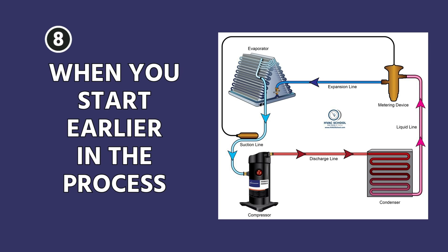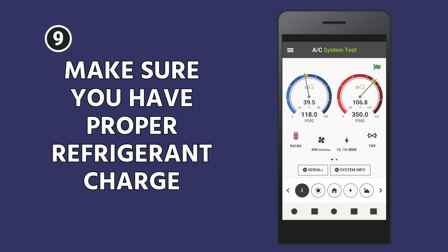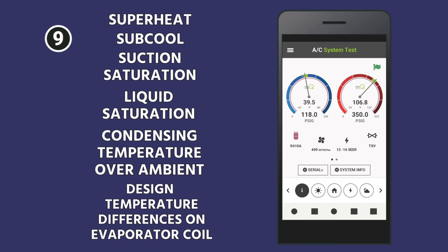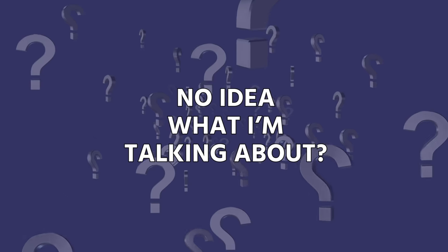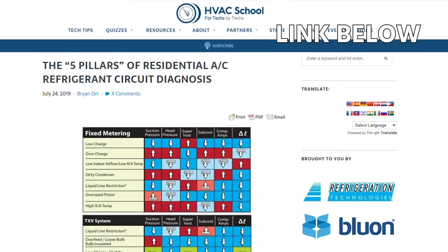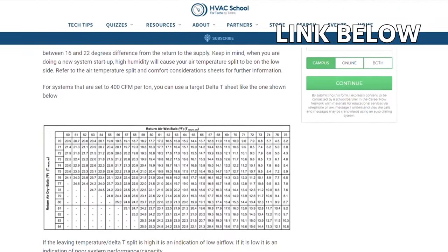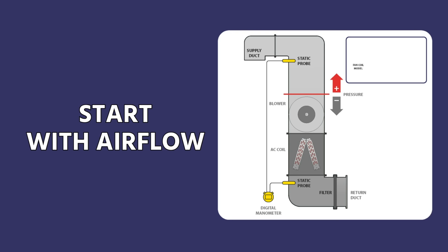When you start earlier in the process and just go with the most obvious things, many times you'll find the obvious problem before you get to scratching your head at the end. Step nine: make sure that you have the proper refrigerant charge. That's where you check your superheat, subcooling, suction saturation, liquid saturation, your condensing temperature over ambient, and your design temperature differences on your evaporator coil. If this is completely over your head, refer to our article on HVACRschool.com that talks about the five pillars of refrigeration circuit diagnosis. But before you get to this point, start with airflow.